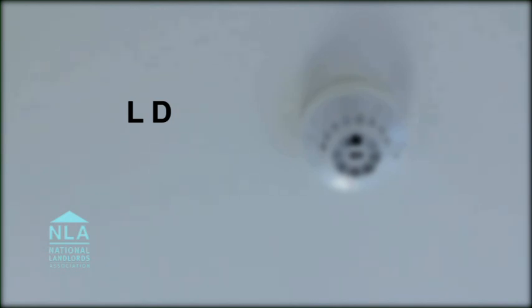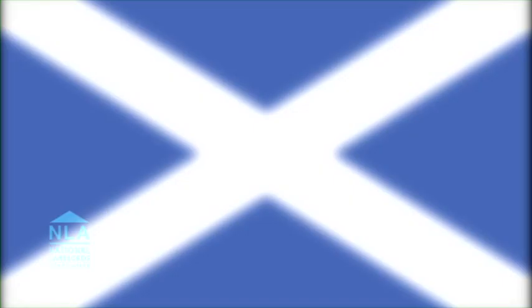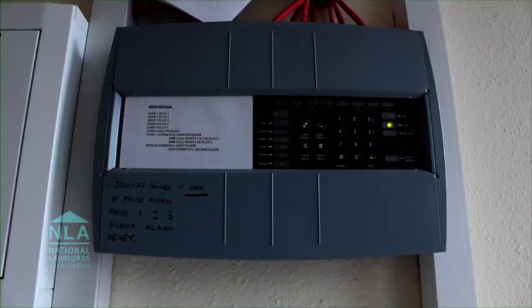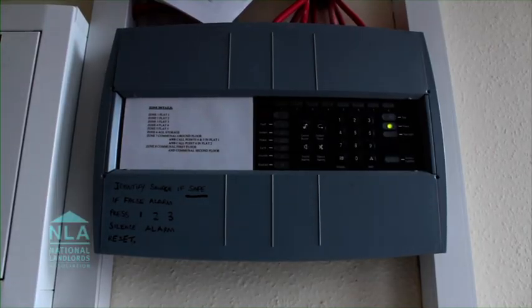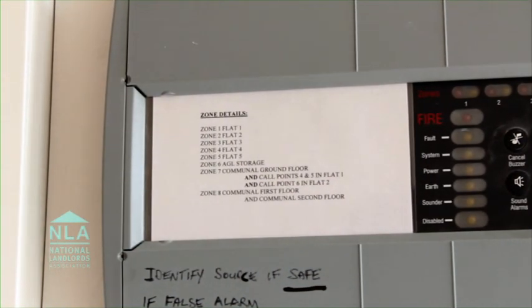For example, LD1 would cover all areas of the building, whilst LD3 covers escape routes only. It should be noted that in Scotland any alarms installed or replaced on or after 3 September 2007 must be mains powered. There are no circumstances where no alarm in a home is acceptable or should be considered as being acceptable.